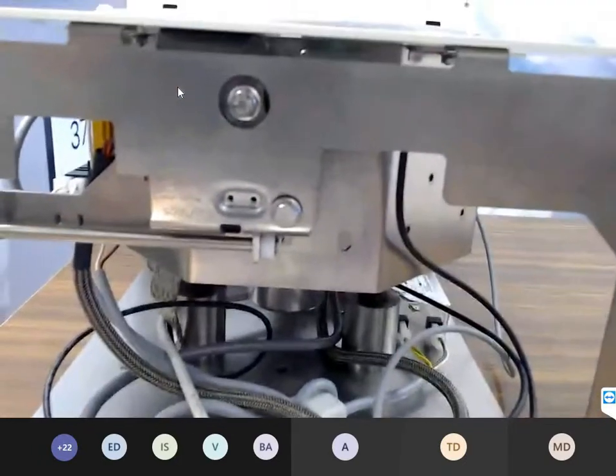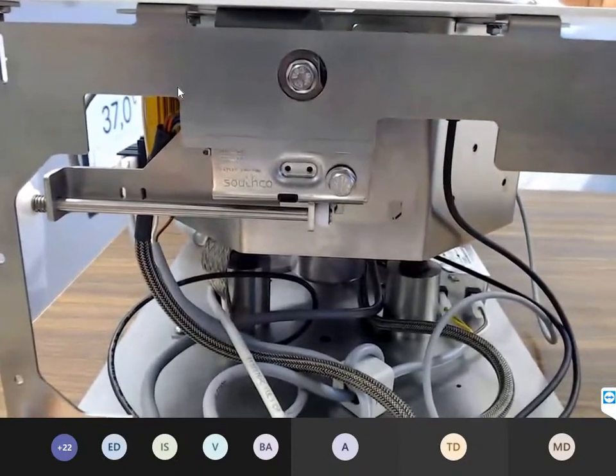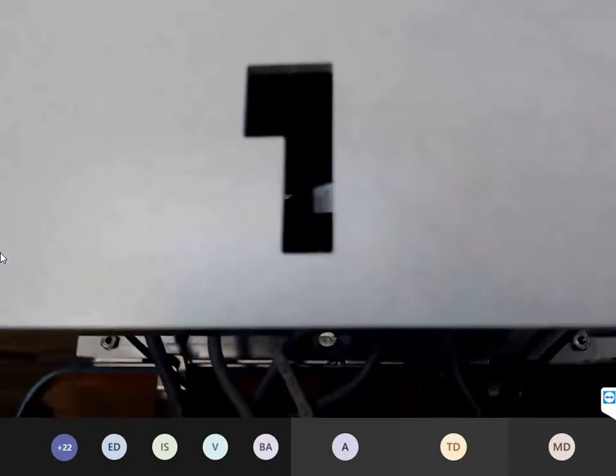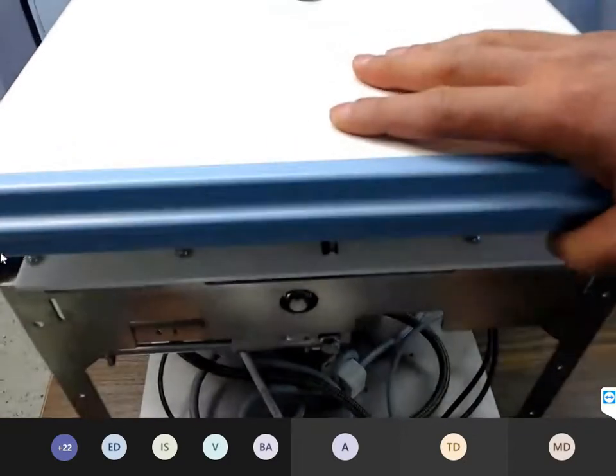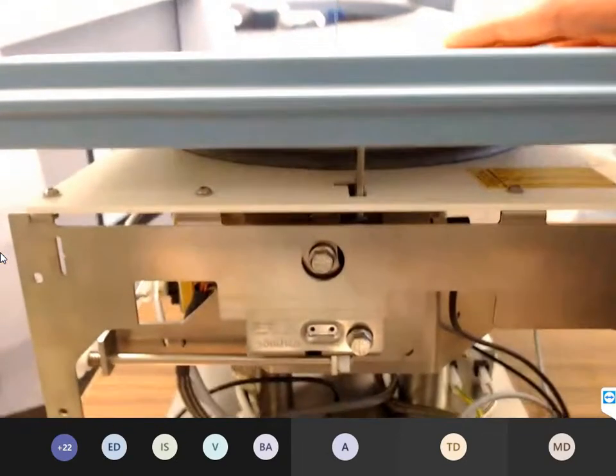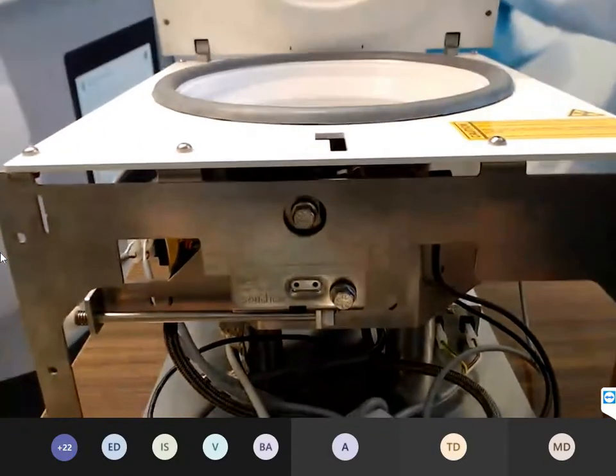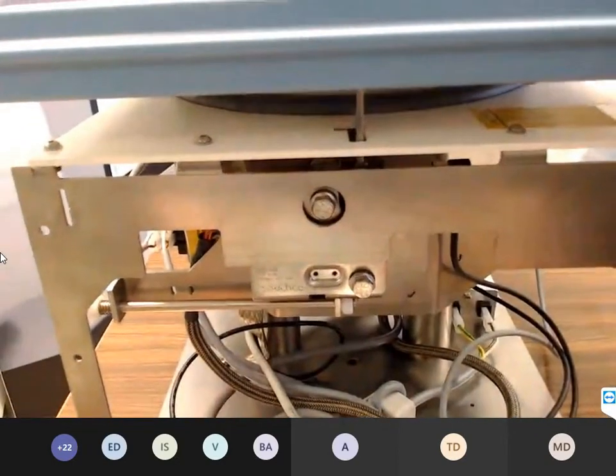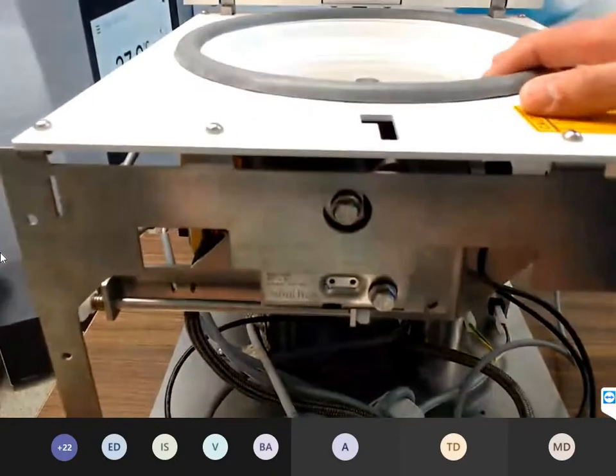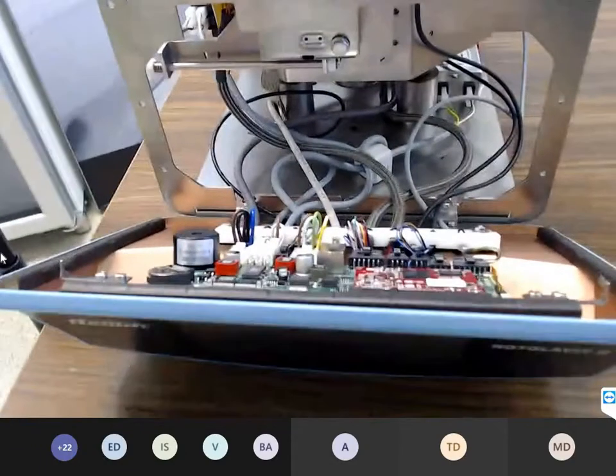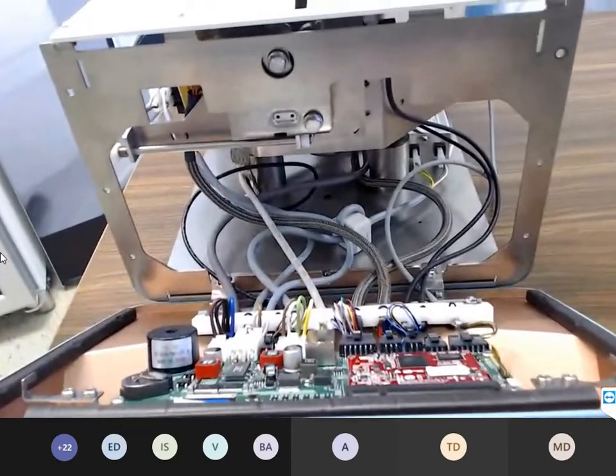We have here on the front the lid lock. Behind the lid lock, you can see from this side, it's an inductive sensor. This inductive sensor reads the lid status, that the lid is closed. The sensor sends a message to the device, and then we see on the display the closed lid, and if the lid is open, we can also see this open state on the display.